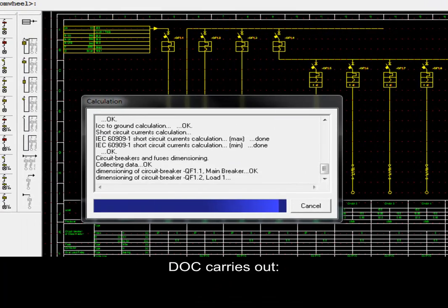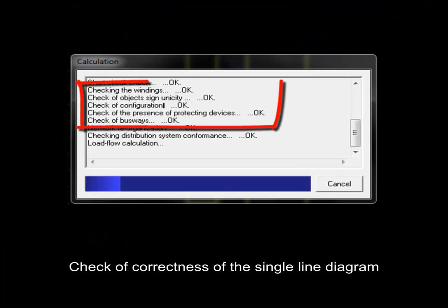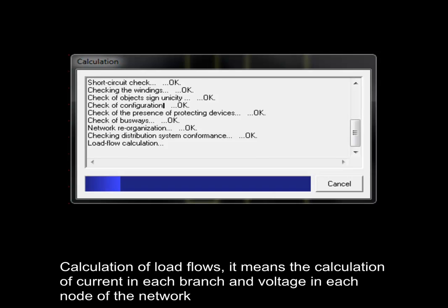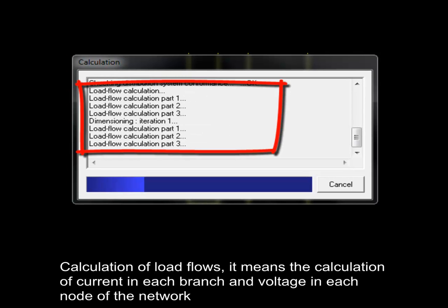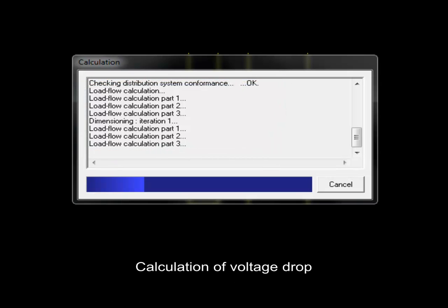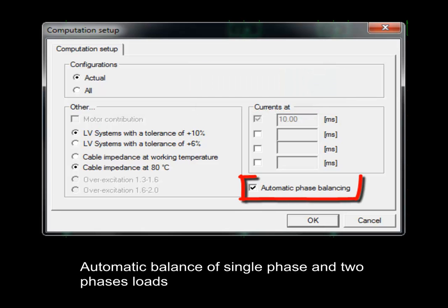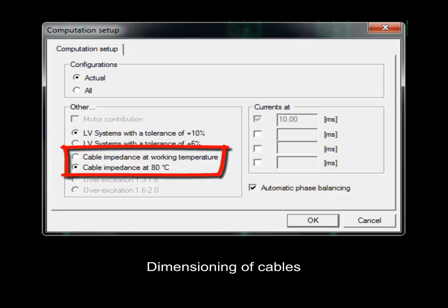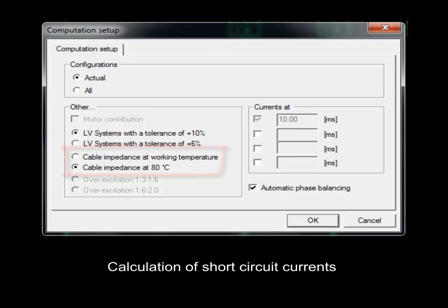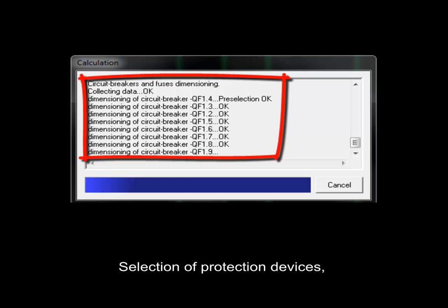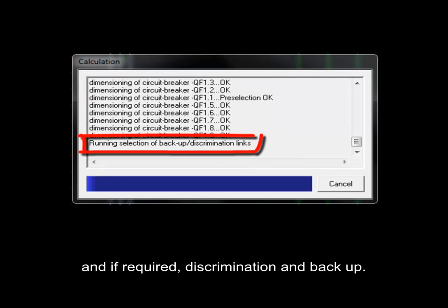DOC carries out check of correctness of the single line diagram, calculation of load flows (the calculation of current in each branch and voltage in each node of the network), calculation of voltage drop, automatic balance of single phase and two phase loads, dimensioning of cables, calculation of short circuit currents, selection of protection devices, and if required, discrimination and backup.